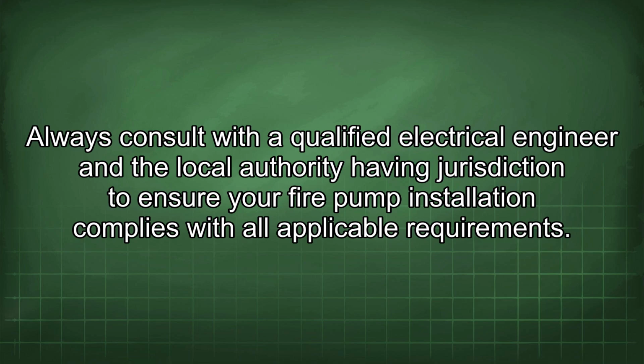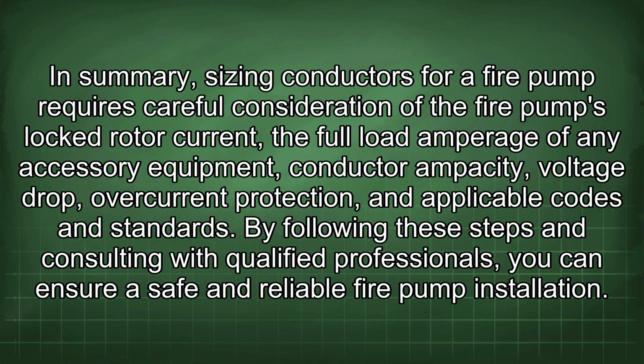with all applicable requirements. In summary, sizing conductors for a fire pump requires careful consideration of the fire pump's locked rotor current, the full load amperage of any accessory equipment, conductor ampacity, voltage drop, overcurrent protection, and applicable codes and standards. By following these steps and consulting with qualified professionals, you can ensure a safe and reliable fire pump installation.